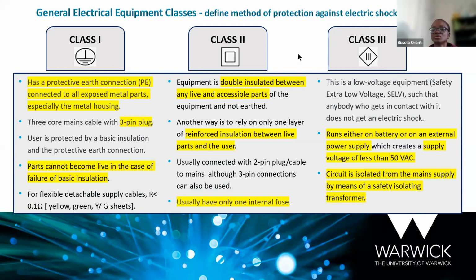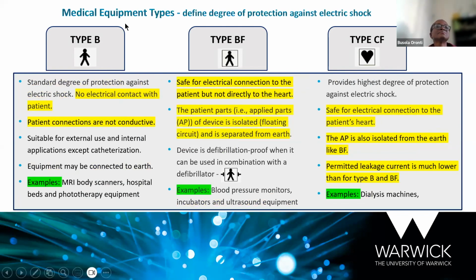So another thing we need to think of is the medical equipment type. And this defines the degree of protection against electric shock. In this case, we have type B, type BF, and type CF. F there means floating, that is, the additional appliances are floating and not connected to the earth. Now, these 3 types are applicable to any class of medical equipment.